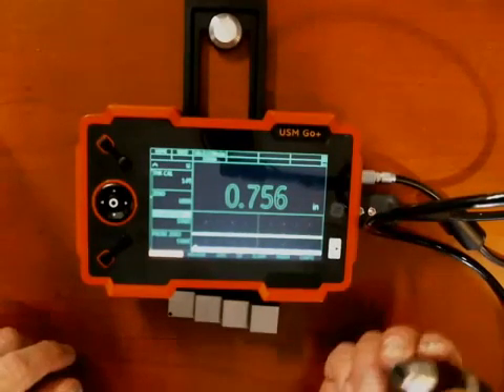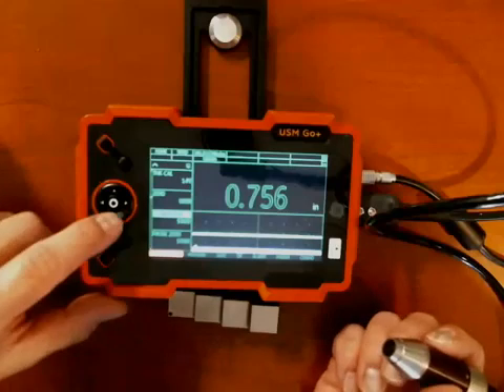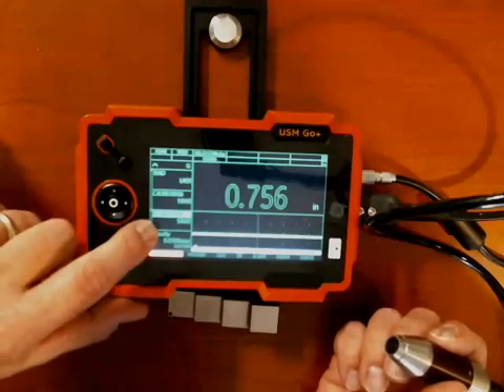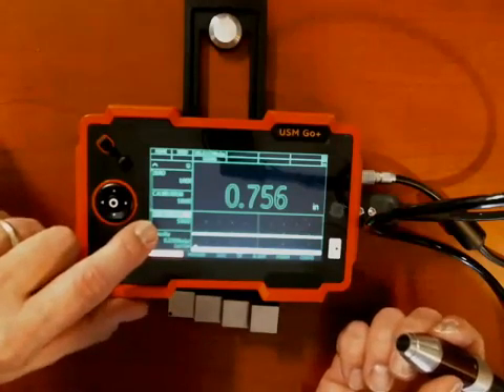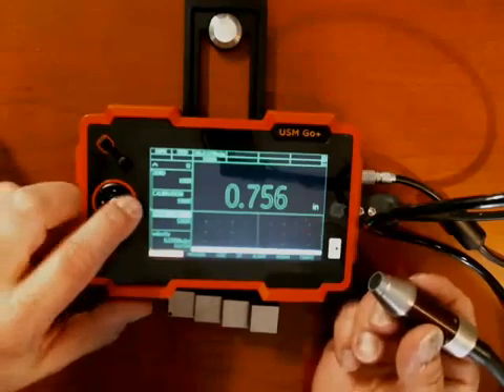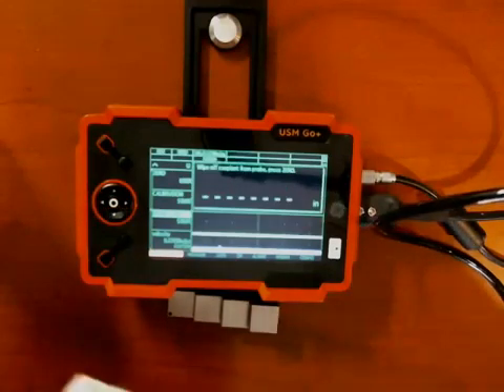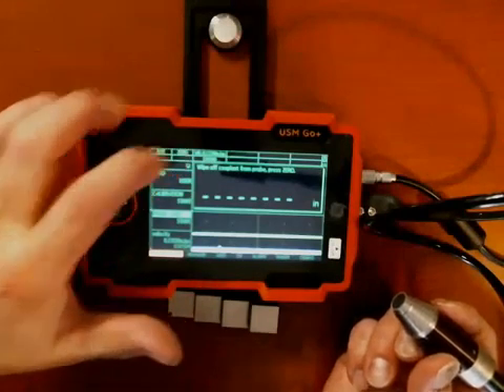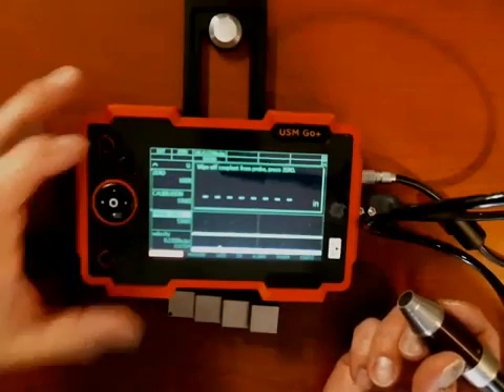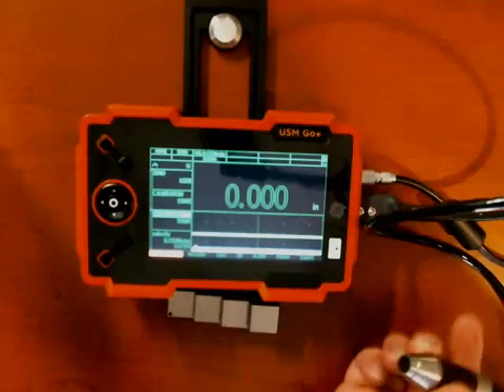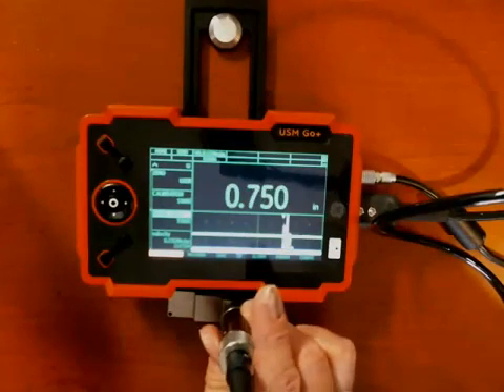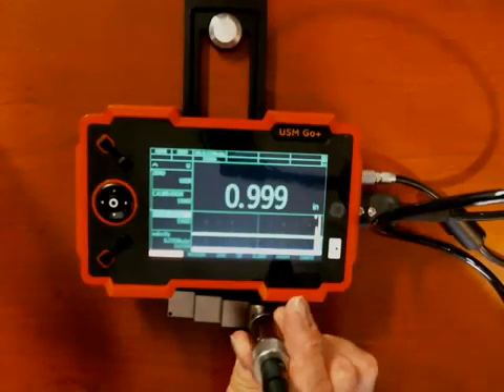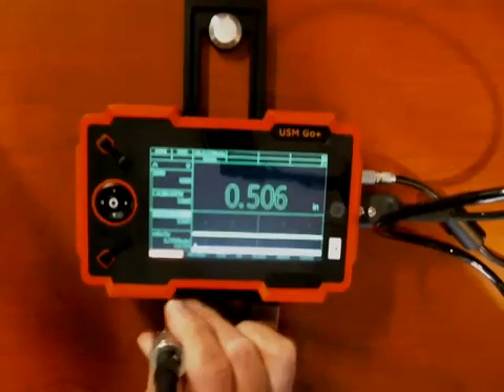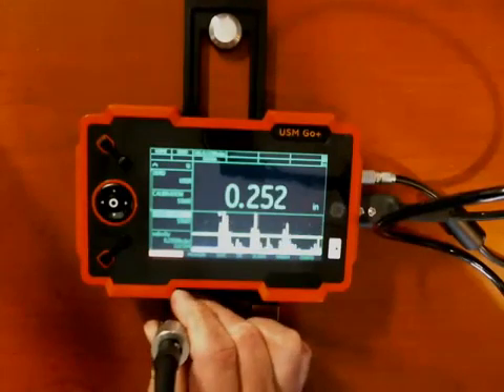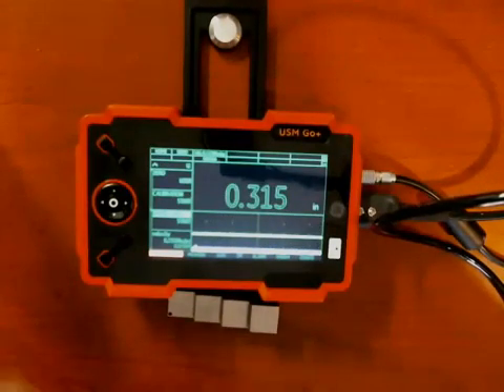If you want to do just the zeroing part of the calibration, there is a place in the menu called Probe 0. I can do Start, and it'll say wipe off the couplant, press 0. This function key is defined as 0 in the corner. Do 0, and that's all complete. So now I can come back, continue taking measurements, and I'm right on where I was before.